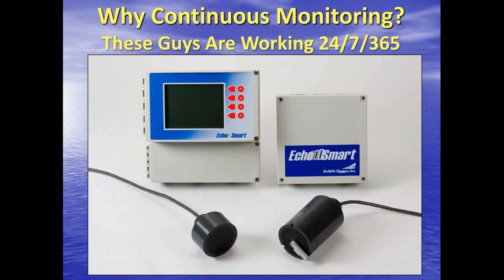The cool thing about that is you don't have to have a wiper, and that splashing action cleans the face of the sensor of a lot of things, actually. It gets all the bubbles off, and it does help keep algae and that type of thing from growing on the face of the sensor. Now, let's say you've got a drinking water plant clarifier or a sed basin. That tank is not going to have a surface skimmer, so we still have to have some way to clean that face of the sensor. So that's where the wiper sensor would come in.